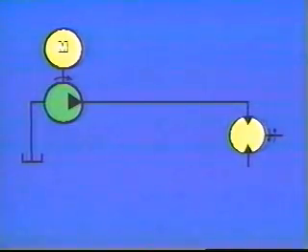And finally, we all know what happens if you stall one. If you're lucky, you'll only blow a fuse. If you're unlucky, the motor burns out. Now, with an electric motor driving our pump, let's see what happens with a hydraulic motor. Since it's a positive displacement unit, if it were to stall, it would not accept any more oil. The pump, also positive displacement, would stall too, since its outlet would be blocked. This in turn would stall our electric motor.